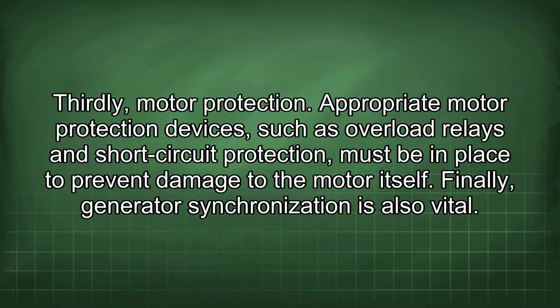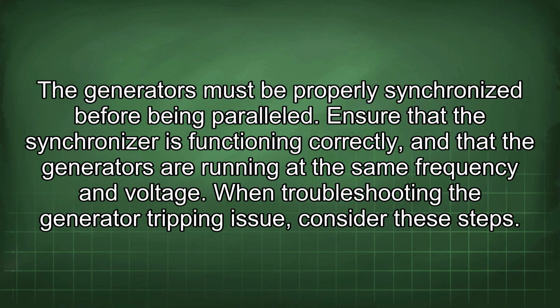Thirdly, motor protection. Appropriate motor protection devices, such as overload relays and short circuit protection, must be in place to prevent damage to the motor itself. Finally, generator synchronization is also vital. The generators must be properly synchronized before being paralleled. Ensure that the synchronizer is functioning correctly and that the generators are running at the same frequency and voltage.